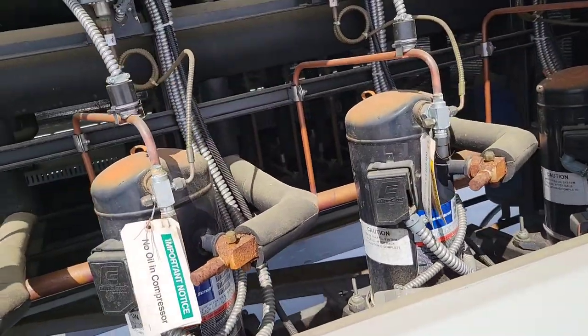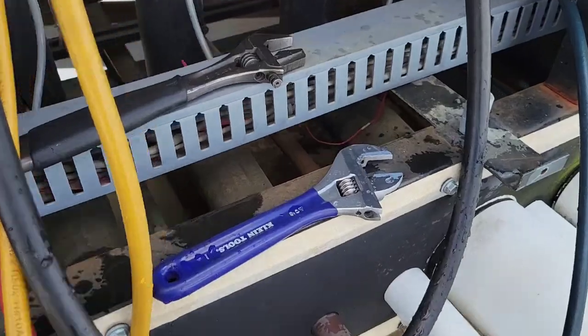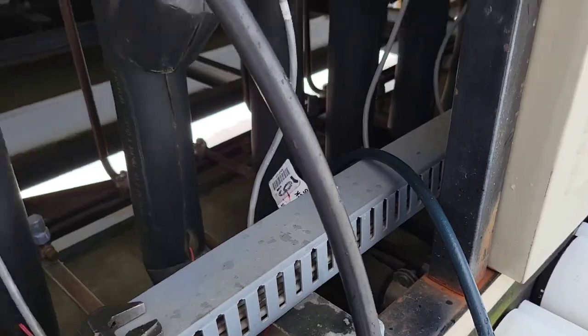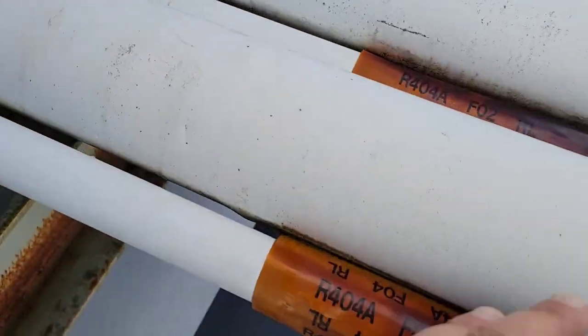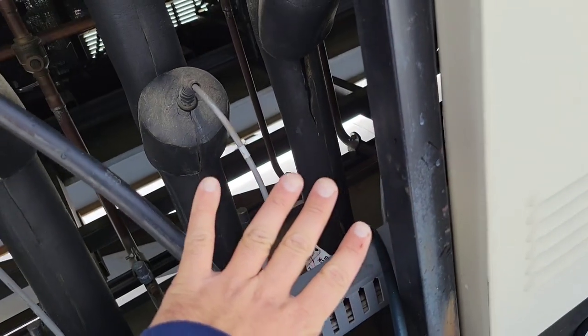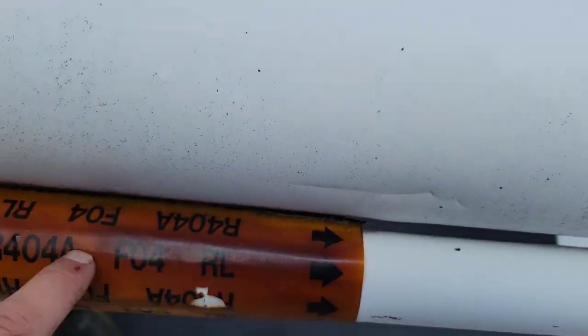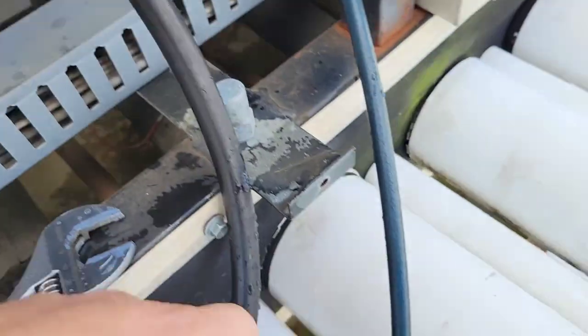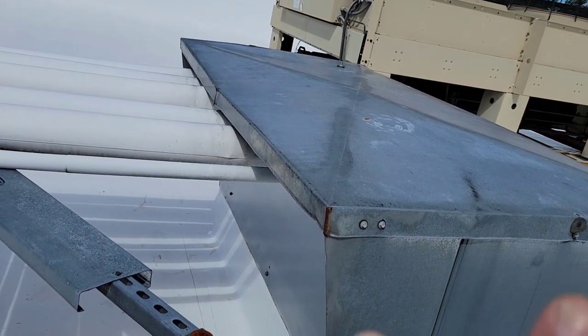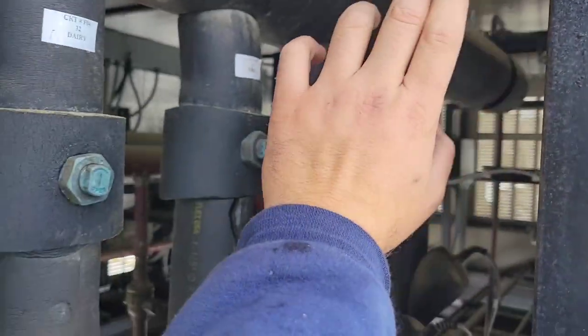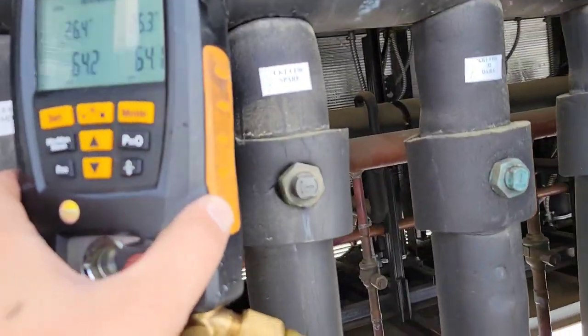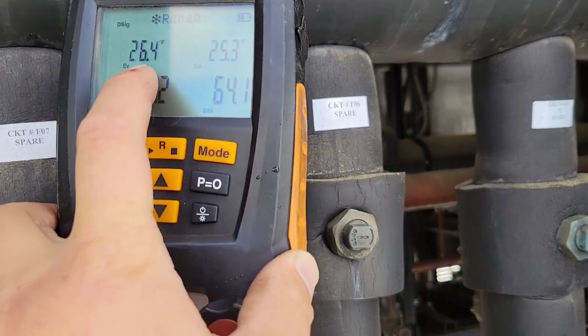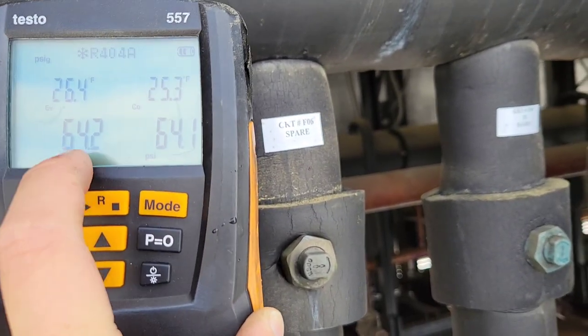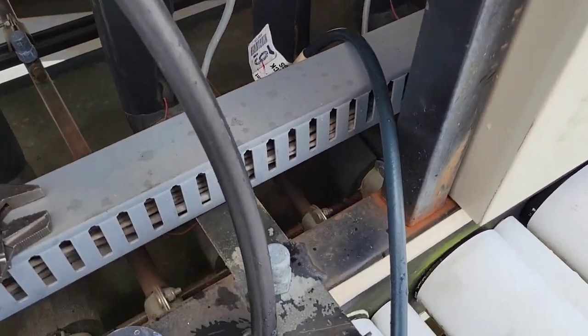I'm going to go over there and see if there's valves over there or if it's a loop system. So I'm hooked up down here, crack that open. Okay, so you can see F4. This side is returning from the case. You can see that liquid line down there. That liquid line goes out to the cases, feeds through the TXVs, goes to the EVAP, and then the EVAP comes back this way, follows that header, and goes into the back of those compressors. So this is a 26 coil, that's what it's targeting, EVAP 26 at 404A refrigerant, right? 64 PSI, so that's our reference when we get down there and check the case.